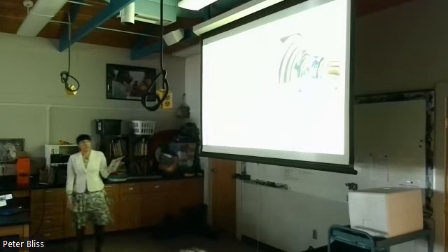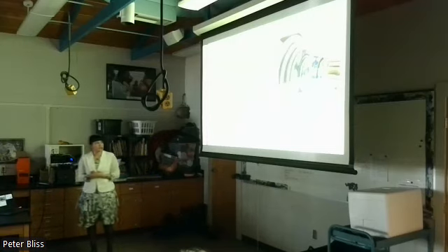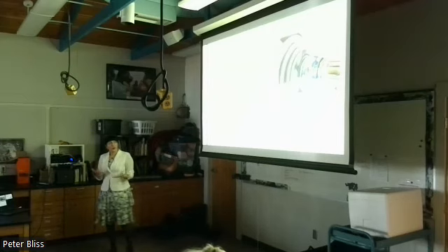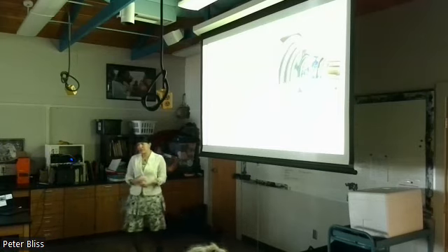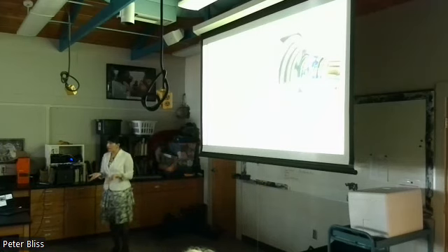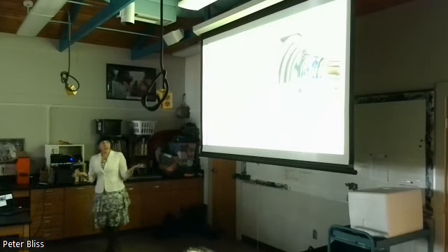So now for the steam turbine, as you see, this is designed for the geothermal power plant. The steam can be corrosive due to many non-condensable gases, as I mentioned, sulfide is one of them. So to protect the rotor blade and nozzle from corrosion, special coatings and materials are used. Same as the well, we know that corrosion and scaling can happen, because when you're drilling a hole inside the earth, you're going to see different kinds of components inside of it, including calcite, carbonate, and other components which cause corrosion. And as you see, this is again the same as the other steam turbines you've probably seen around.